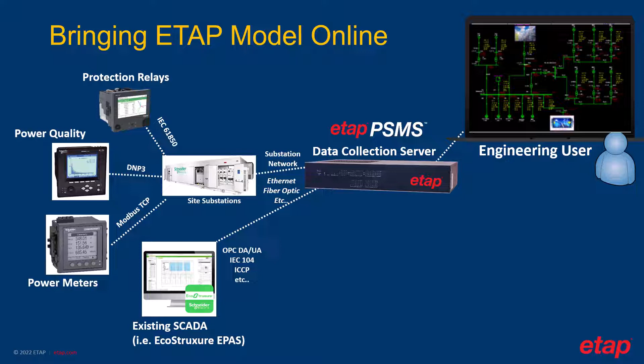There are some cases where direct connectivity is not available to the electrical devices, or there is already an existing SCADA in place. Examples of these SCADAs are the Schneider EcoStruxure Power Automation System, EPAS, or Schneider EcoStruxure Power SCADA Operation, PSO. In these cases, when a SCADA is already in place collecting data, ETAP just establishes communication to your existing SCADA to bring data into ETAP.